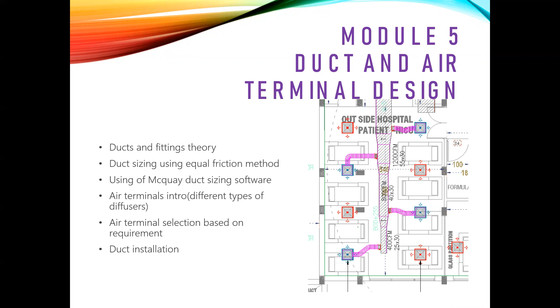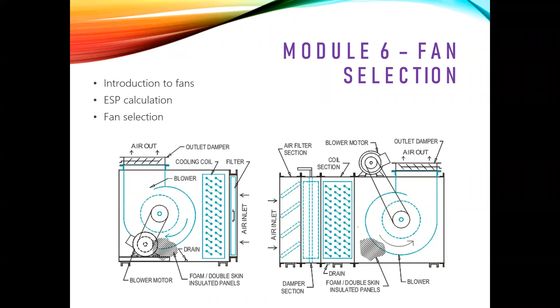After that, this is one more topic. As mechanical engineers, you will have an idea about fans, right? Different types of fans, axial fans, centrifugal fans, etc. From the load calculation data, we can directly select a suitable fan. Before that, one more piece of data is required, from the CFM and everything. There is one calculation called the ESP calculation. It's also one of the major points as an HVAC engineer. You will be using it very often. As an HVAC engineer, mechanical engineer, or MEP designer, you should know this ESP calculation. After the calculation, you will have an idea about how much capacity the fan needs, and based on that, you can select a fan of your choice which is suitable for the project.